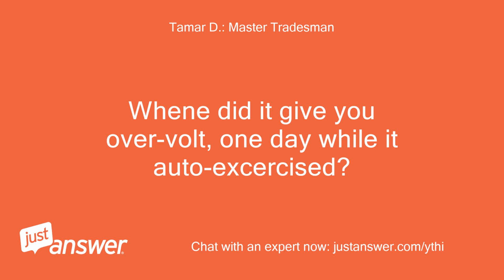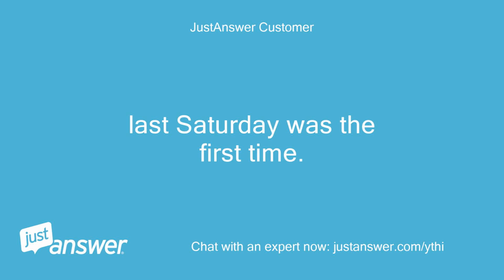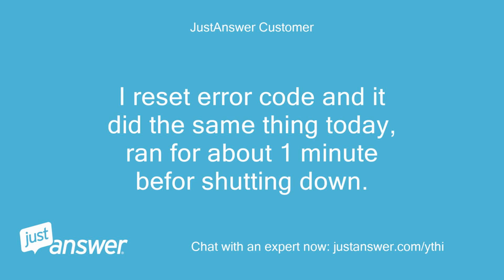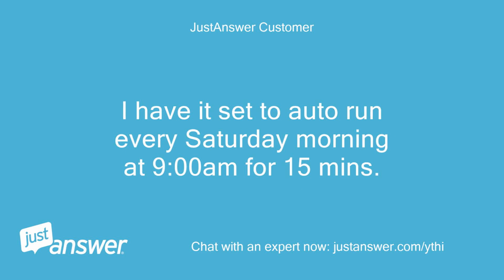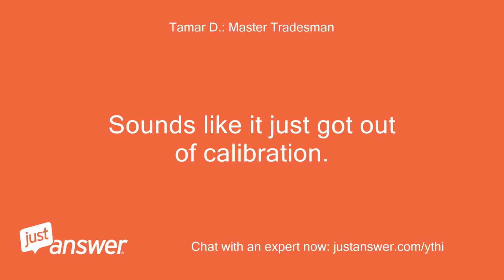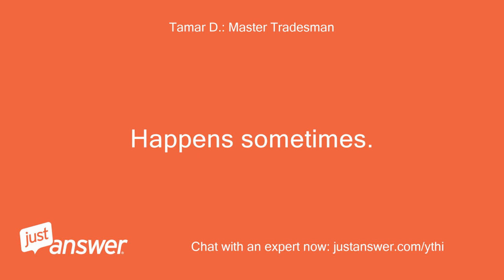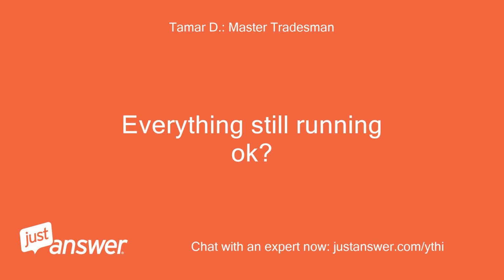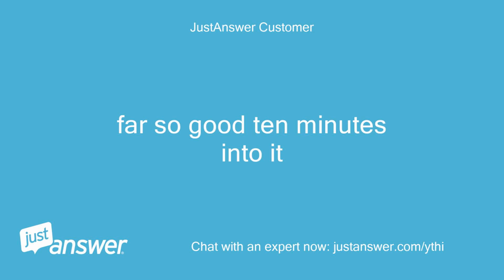When did it give you the overvolt? One day while it auto-exercised. Last Saturday was the first time. I reset the error code and it did the same thing today, ran for about 1 minute before shutting down. I have it set to auto run every Saturday morning at 9 a.m. for 15 minutes. Sounds like it just got out of calibration. Happens sometimes. Everything's still running okay. So far so good, 10 minutes into it.